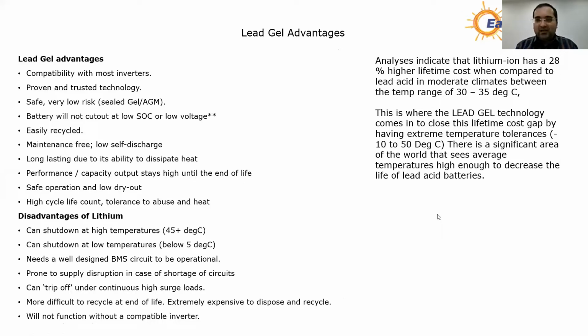So currently, most major manufacturers have this analysis that indicates where exactly you should be using lithium ion as compared to tubular gel type batteries, because the lithium ion battery has a 28% higher lifetime cost when compared to a lead gel battery in moderate climates, which have a temperature range of between 30 to 35 degrees centigrade.